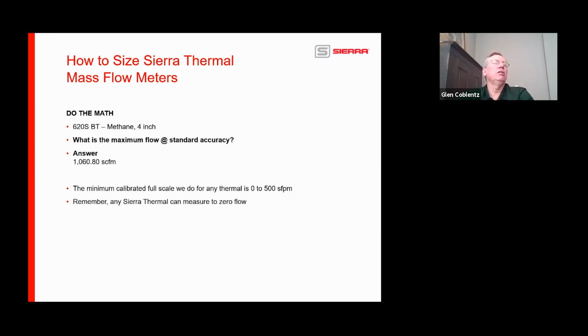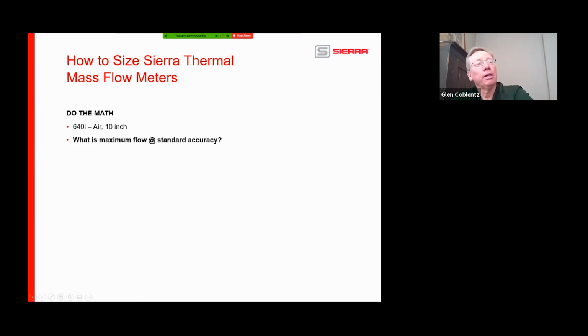If the customer says, no, I think my flow rate is 10,000 SCFM, well, the first thing you're going to probably tell them is, well, I think that's physically impossible, but maybe there's something else to it. Like, for example, his methane flow is at 1,000 PSI. Now that might be possible, but we're not going to measure it with a 620S BT. So as you come up with these answers, it helps validate the application, and it validates that you have the proper meter, or it opens up all kinds of other questions about, do I have the right product for this application? Let's do it again.